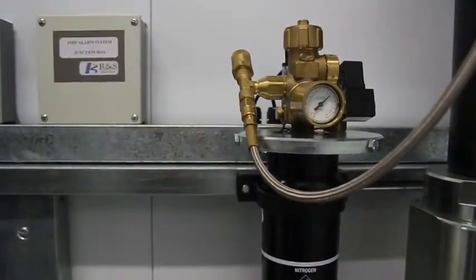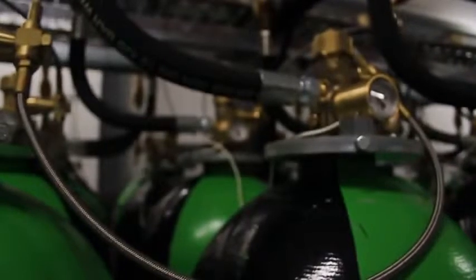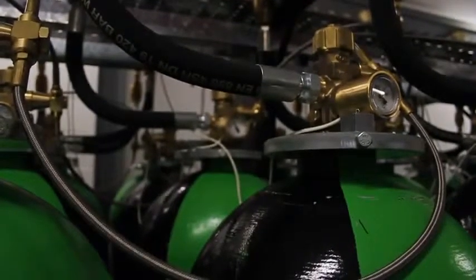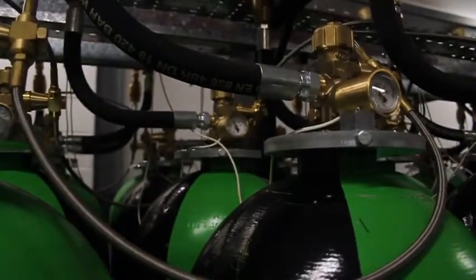Fire is probably the key risk in any data centre. A lot of investment has been made in our fire protection systems. We use an inert gas system in all of the tech halls. We use a high mist system in our DRUPS area because this is particularly good at dealing with diesel fire issues. And we've installed a VESDA early warning system throughout the facility at both high level and underfloor. All of this capability allows us to detect an incident early and to extinguish a fire very, very quickly if it does occur.